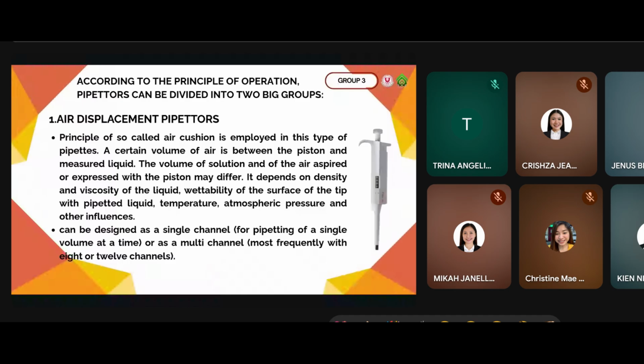According to the principle of operation, pipettes can be divided into two big groups. First, the air displacement pipettes. The principle of the so-called air cushion is employed in this type of pipette. They can be designed as a single channel or as a multi-channel. Air displacement pipettes work using an air cushion between the piston and the liquid. When the piston moves, it pushes or pulls the air, and this air in turn moves the liquid.